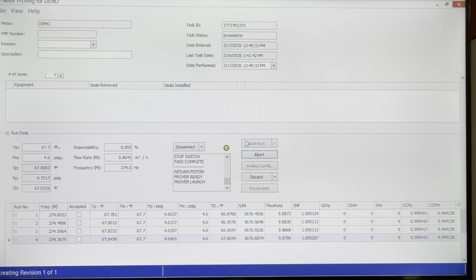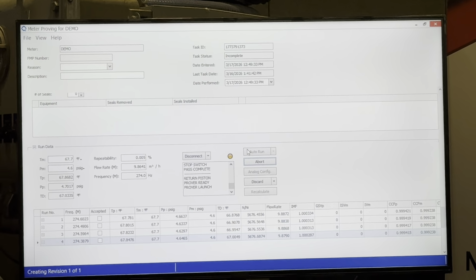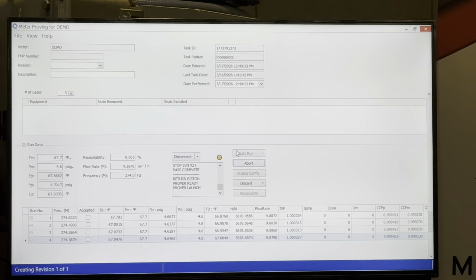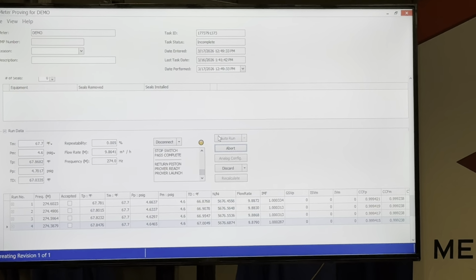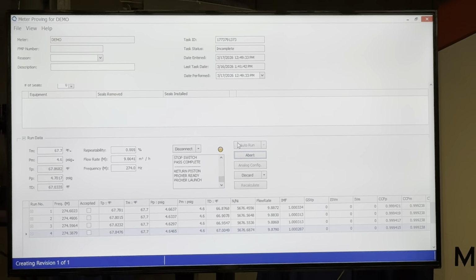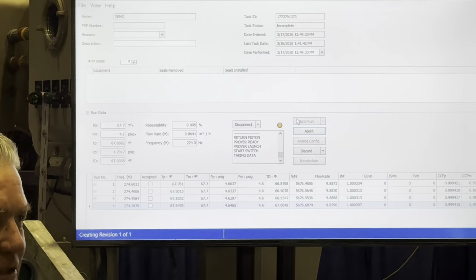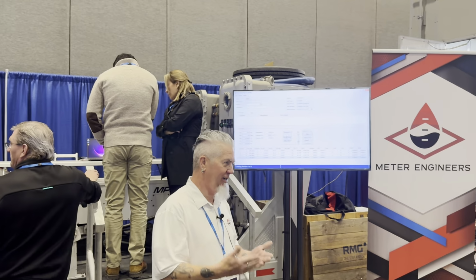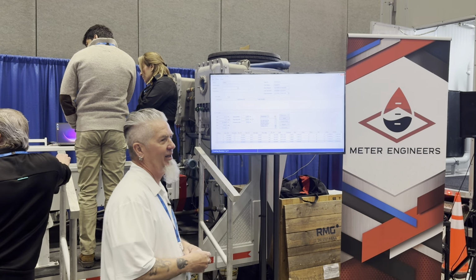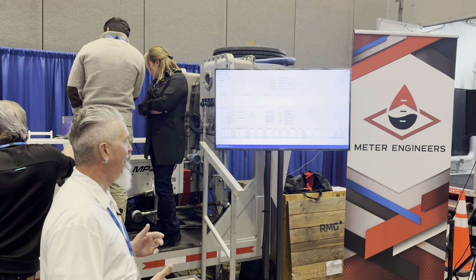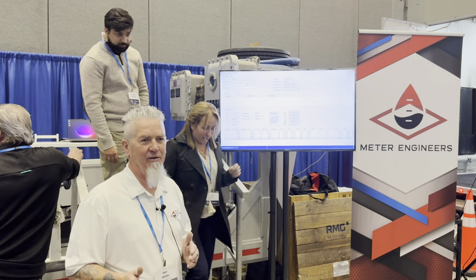One thing you gotta watch out for a lot of times, like I said, when you're witnessing something, is that when the guy's proving, he should, every pass, be glancing at his temperatures and his pressure. Make sure that nothing has gone south, and most of all, make sure nothing's leaking. You can have a drip between your meter and your prover, and if it's a constant drip or a constant run, there's a good chance it'll come in. It'll be close to your .05, but it can come in, but you're not counting everything. And if you're running a 4-way or some kind of seal, you want to make sure that seal is sealed and nothing's bypassing your seals.